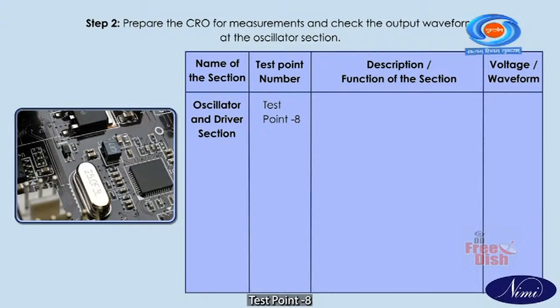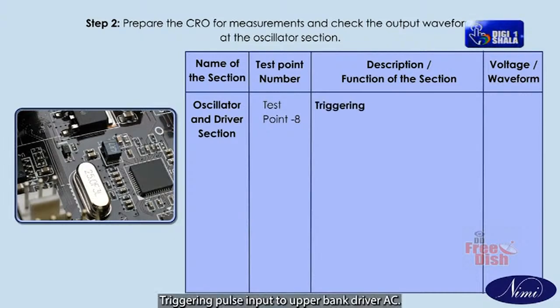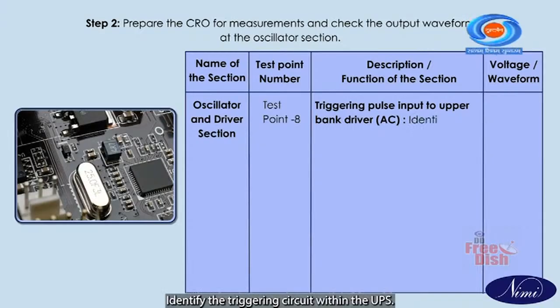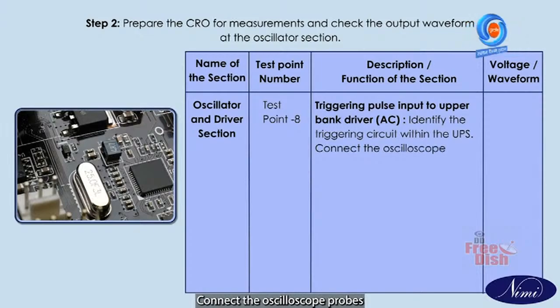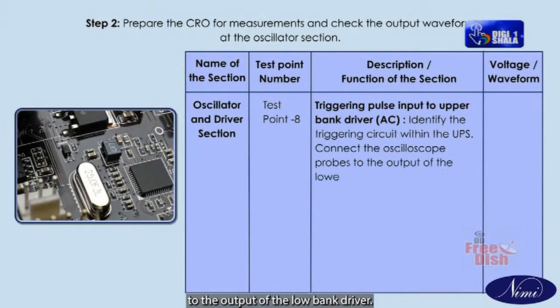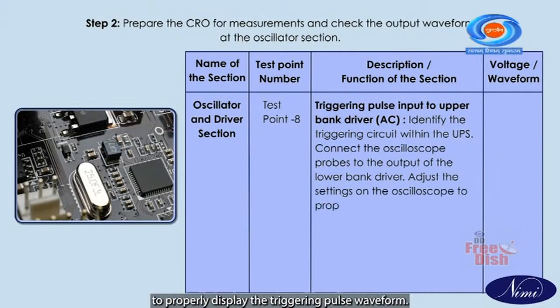Test point 8. Triggering pulse input to upper bank driver AC. Identify the triggering circuit within the UPS. Connect the oscilloscope probes to the output of the lower bank driver. Adjust the settings on the oscilloscope to properly display the triggering pulse waveform.